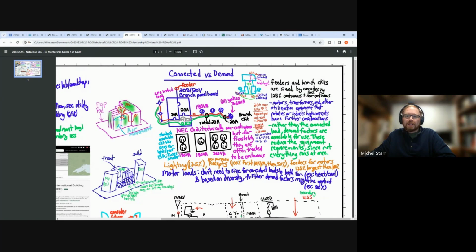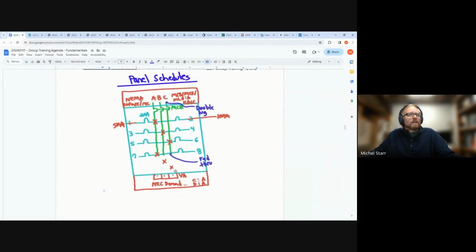The consideration being that the wire is being heated up continuously. So the product listings and all of that are in this mindset of not letting fire happen, as well as these breakers being molded case with thermals, and so there's a physics involved in here of continuing to have current flow. So that's at the bottom, those would be added up.